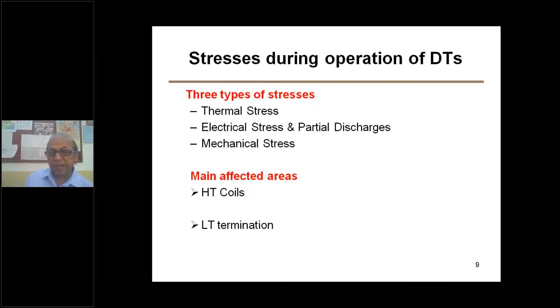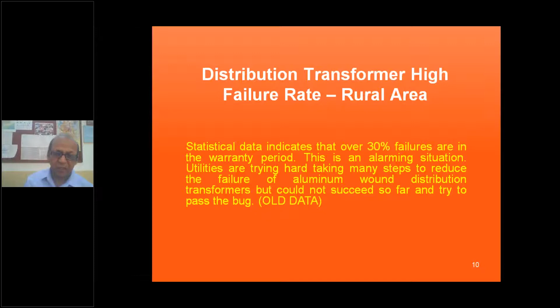Now why are we discussing the HT coils and LT termination? Because for HT coils, as I have shown you in the pictures, the failures are taking place between the spacers. For LT termination, I will tell you a practical example of what is happening to LT termination, just after a couple of slides. Now you see the state that 30% failures are in the warranty period, which is quite an alarming situation for the aluminium wound transformers. Now the temperature rise is also an issue that we see.